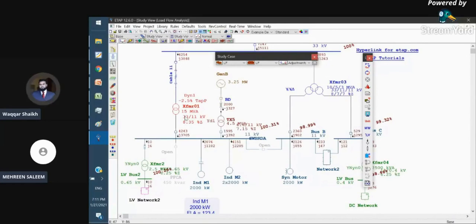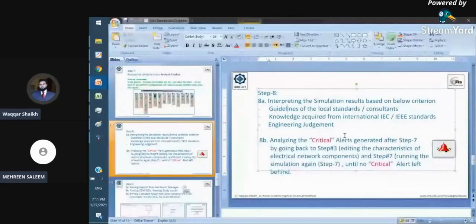So now, in step number 8, we are running the simulations. We will be shown critical alerts based on our alert settings inside the study case toolbar, such as 95% and 100%. By analyzing those results, we can go back into edit mode, do some fine tuning, change some network configuration, and then come back and run the simulations again until we get green results, meaning no critical or marginal alerts.